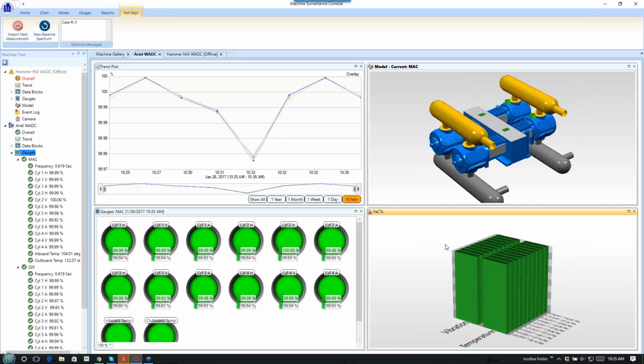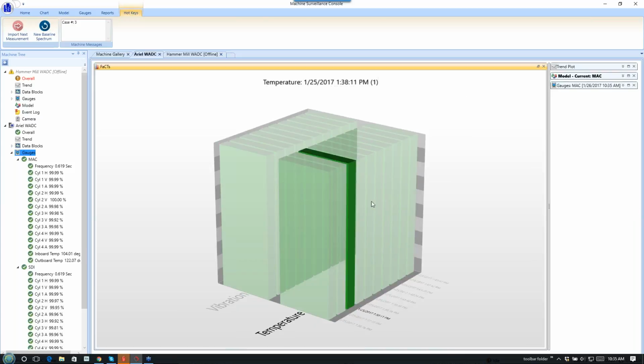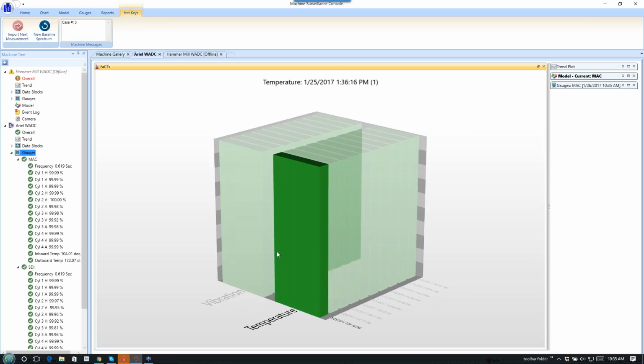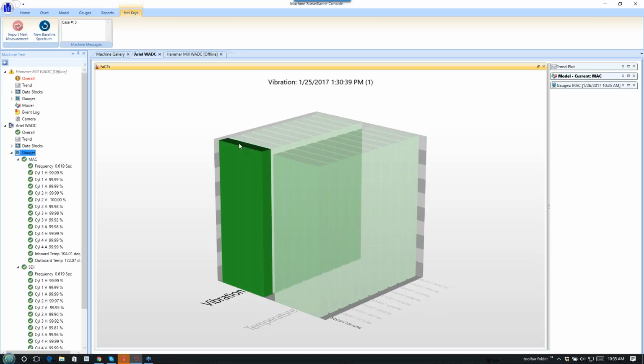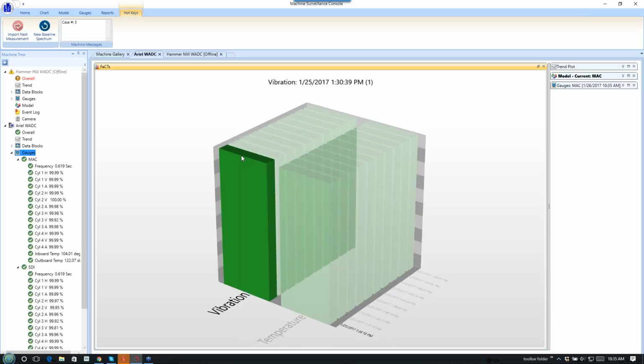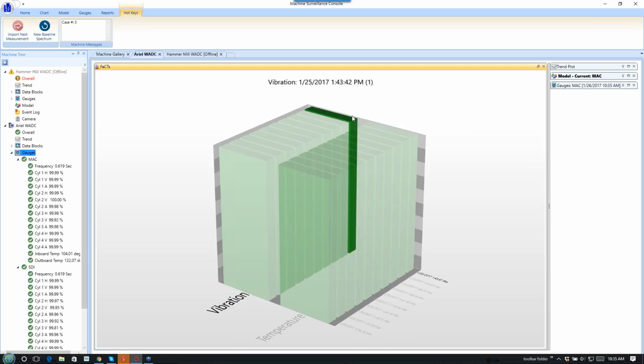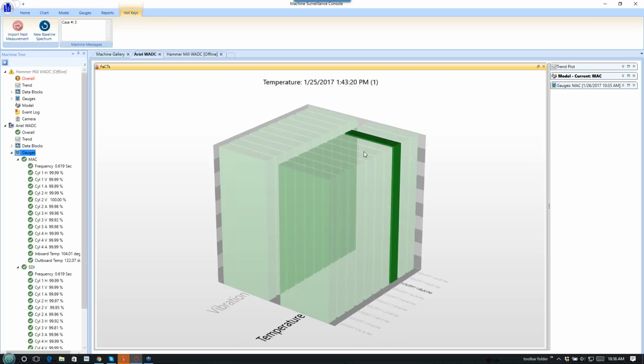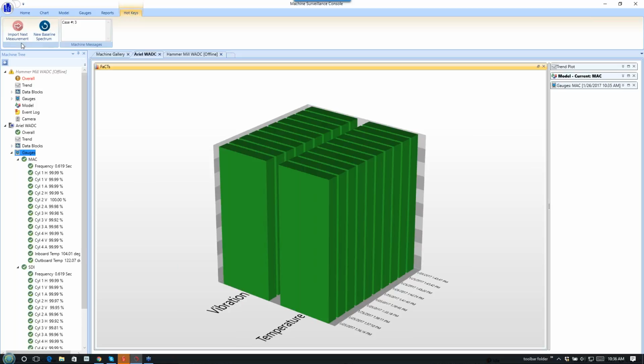And down here, I've got two FaCTs bars. One of them is showing my vibration, and it's saying that these vibration levels measured by SDI are all the same as what you've got in your database, and the temperatures are all the same. So as I take data, basically this is my pass-fail test. It's saying this data is coming in exactly the same. So that means the spectra, now here you can see the spectra all changed at 99.